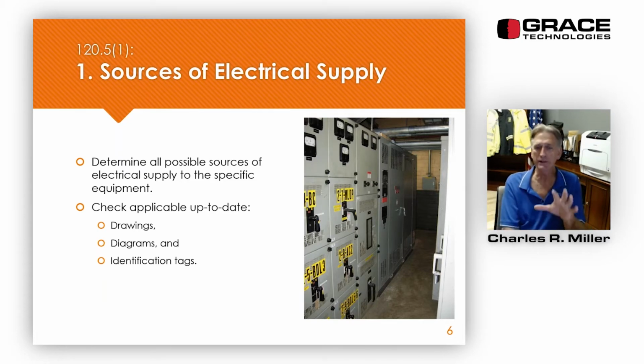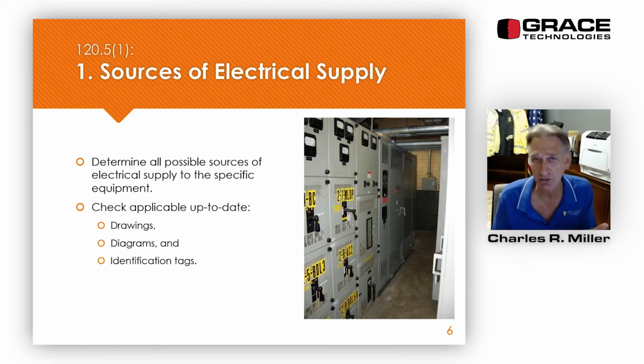And so, all right, if we look on a panel schedule, we see a breaker, or in a motor control center, we see the bucket that's labeled for the motor that we want to shut off. So we turn it off either on the regular breaker or in the MCC bucket disconnect. After we turn that off, can we trust our life that that is labeled correctly? I see everybody, well, I don't see you, but I know you're shaking your head. No, you cannot. You do not trust your life to labeling. But it's a great place to start.